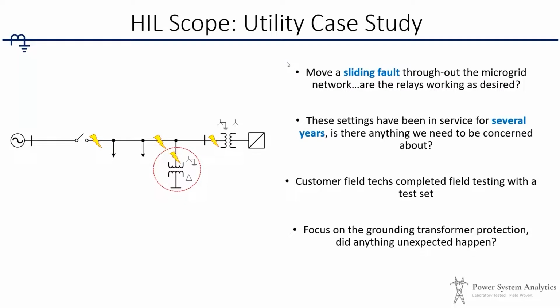So the HIL scope of study was to move a fault around in the network. So slide a fault throughout the microgrid and observe the results. Did the right protection operate? Did things coordinate properly? Are we seeing anything that's not desired? Did something not trip when it was supposed to? Any major things that we need to follow up on? So that was the scope. Pretty simple as far as it goes.